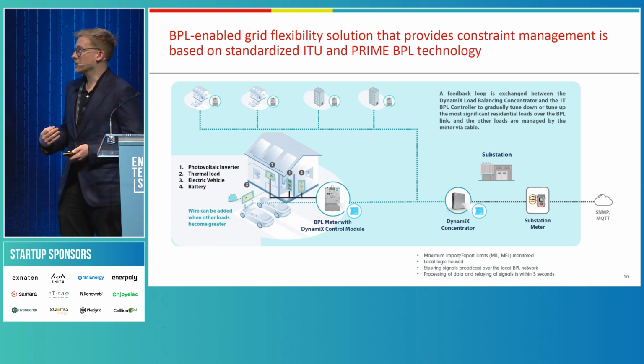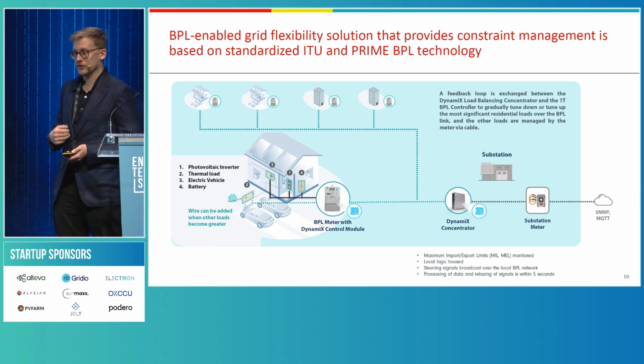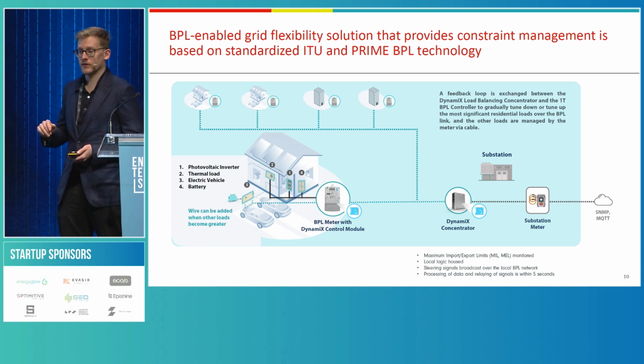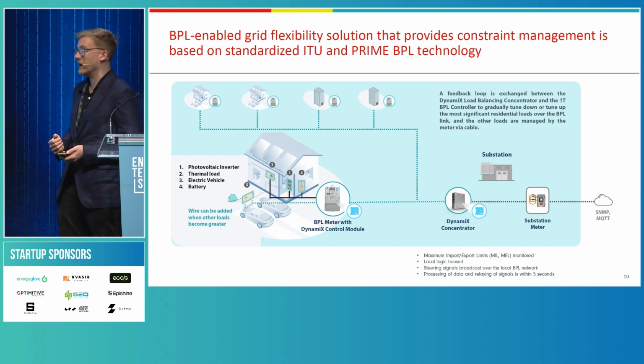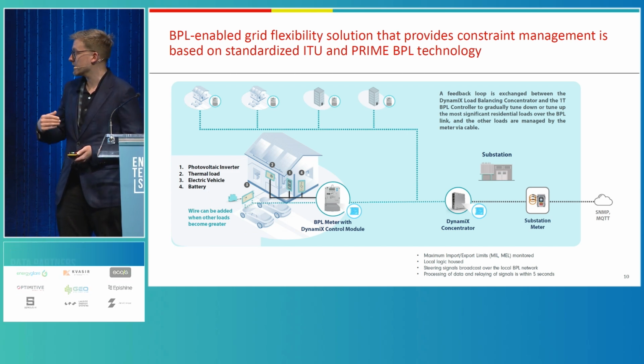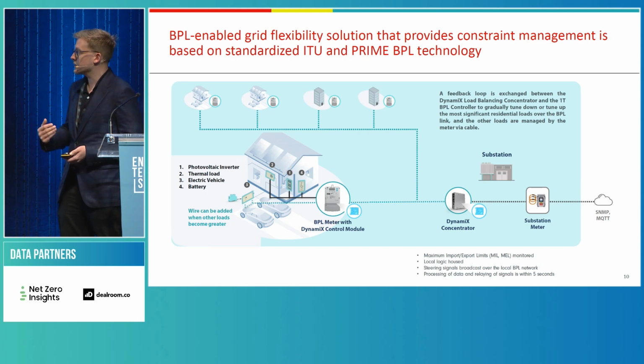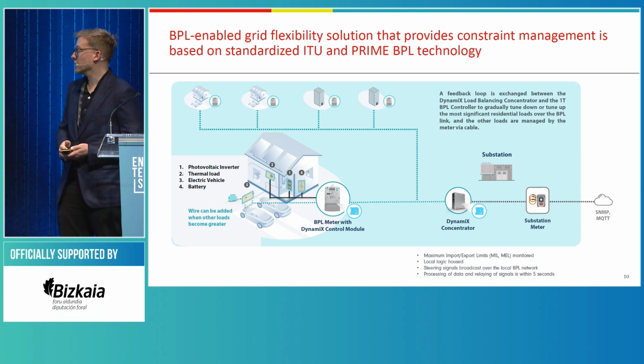We're able to make the local flexibility aggregator compliant with, for example in the UK, the G100 regulation. This allows us to modulate and steer those low carbon technologies, rather than simple on-off switches, ramping up during power outages or when there's overload on the secondary substation transformer. We can protect the transformer from overload and provide the DSO with an additional 35% capacity on the low voltage.